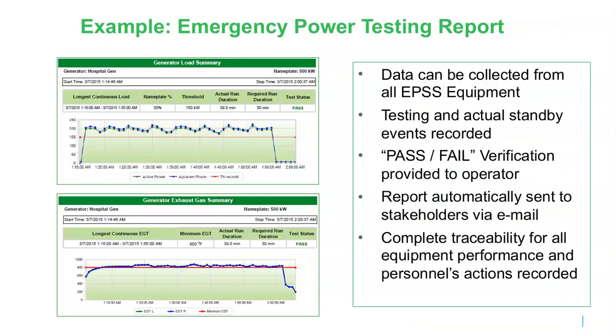So this is a part of the report that's probably the most often viewed. It's whether or not it passed or failed the generator monthly 30% for 30 minutes. And what you're seeing here at the top left-hand side, we do have a plot of the kW of the generator logged continuously over that time, verifying that there was a minimum of 30% for 30 minutes.